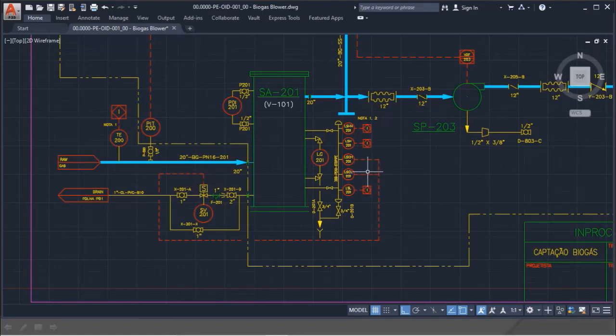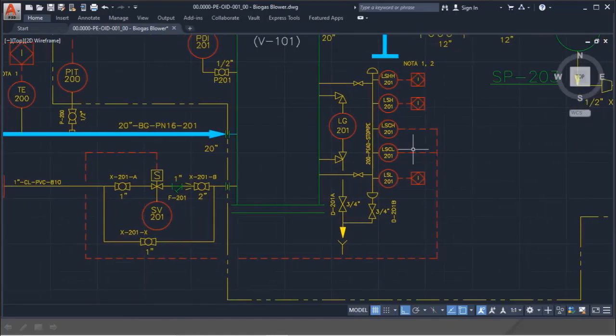So at the LSCL, the command is to close the valve, and as liquid accumulates, the liquid will reach the LSCH, and the command is to open the valve. When we open the valve, we start to decrease the level of the separator vessel, and when it reaches the LSCL again, the valve will close.